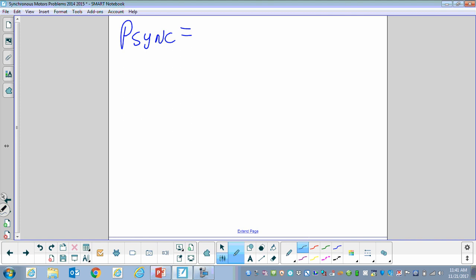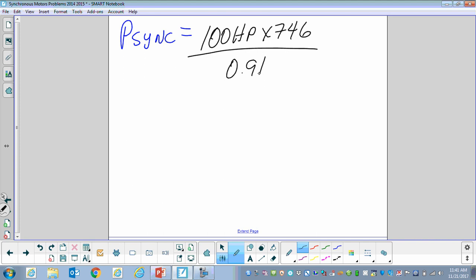Again, we need to figure out power input. We take 100 horsepower, multiply by 746, and then divide that by our percent efficiency, which is 0.91. Done correctly, we should come out to 81.978 kilowatts.